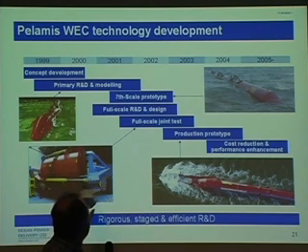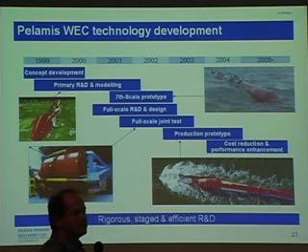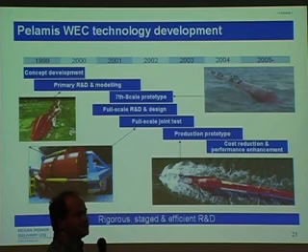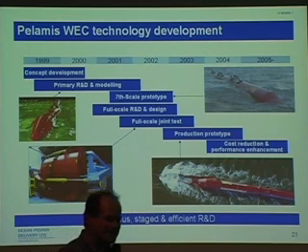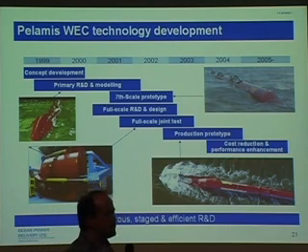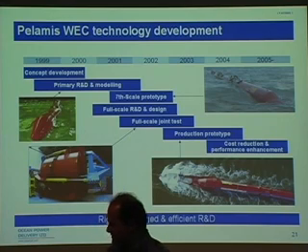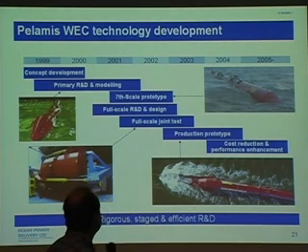So we had a 2 megawatt power connection coming in here, driving a hydraulic power takeoff system that then acted around this fulcrum here, with our power takeoff system converting that mechanical movement back into electricity. Not surprisingly, there was far less electricity coming out than was going in, because otherwise we'd really have solved something. But it gave us very good confidence in the overall power takeoff system and the efficiencies we were getting. The overall mechanical to electrical efficiency is of the order of 70 to 80%.